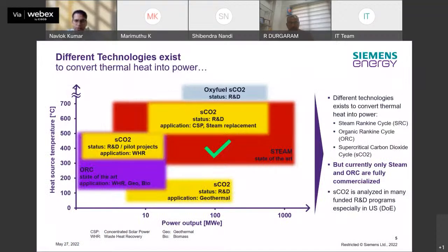Different technologies exist to convert thermal heat to power, such as steam Rankine cycle or SRC, organic Rankine cycle or ORC, and supercritical carbon dioxide cycle or SCO2. The supercritical carbon dioxide cycle is largely in development phase. The ORC-based technology is limited to smaller power generation units rated up to 30 megawatt of capacity and is very commonly used for low temperature waste heat recovery. Currently, only SRC and ORC technologies are fully commercialized, and SCO2 is analyzed in many funded R&D programs, especially in US by Department of Energy.